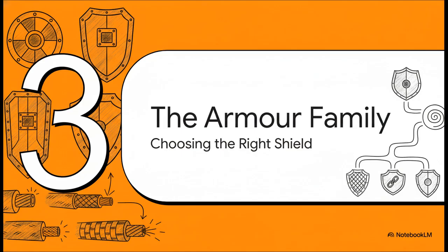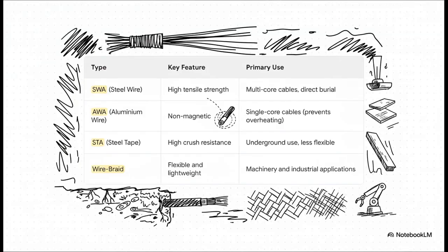But here's the thing, not all armor is the same. It's not a one-size-fits-all deal. You wouldn't use the same shield for every type of battle, and it's the exact same logic with these cables. There's a whole family of different armor types, and picking the right one for the job is absolutely critical. So the one you're going to see most often is SWA, which stands for steel wire armor. It's got an incredible pulling strength, what we call tensile strength, which makes it perfect for just burying it directly in the ground. But if you have a single core cable, you have to use AWA, or aluminum wire armor. And there's a fascinating bit of physics as to why, which we're about to get into. Then there's STA, or steel tape armor, which offers fantastic resistance to being crushed. And finally, you have the more flexible wire braid armor, which is great for things like connecting to heavy machinery that might be moving or vibrating.